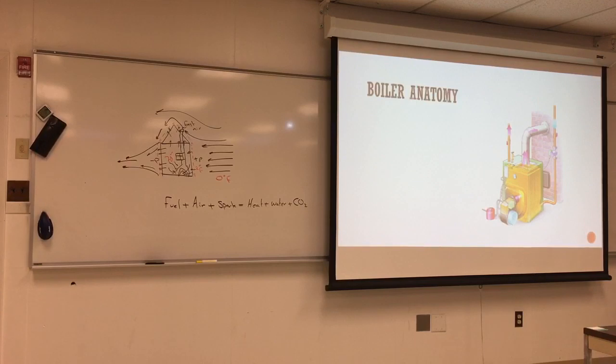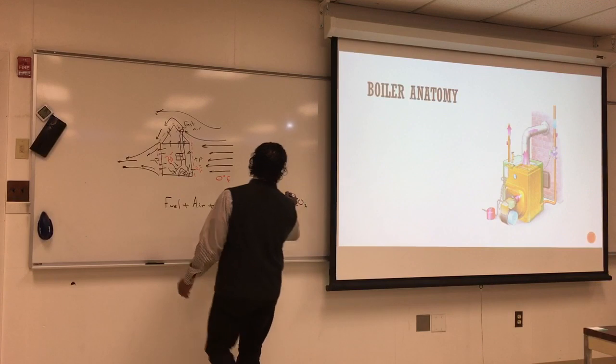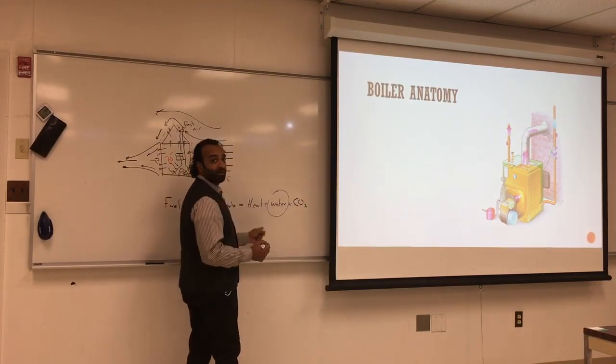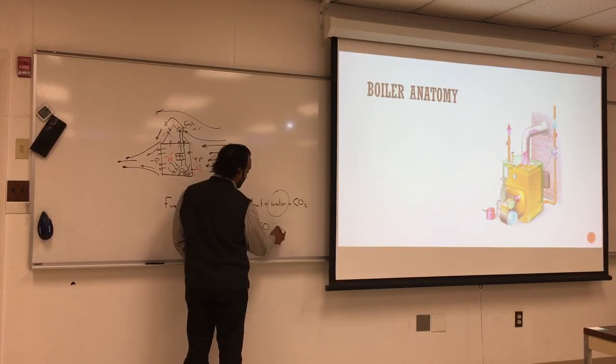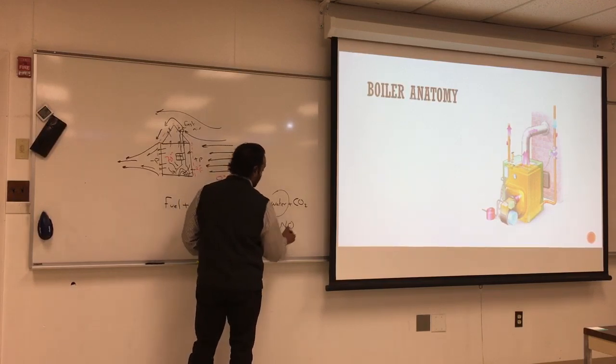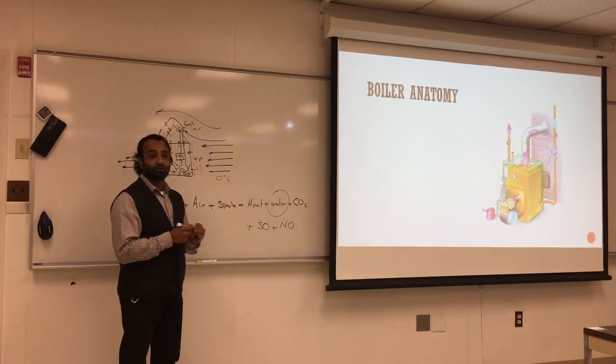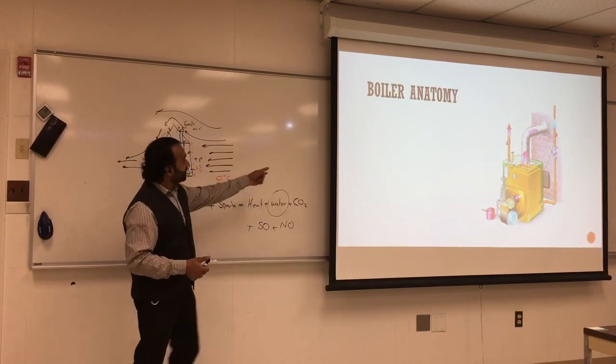What happens if your temperature at the flue pipe is 350? You'll think, hey, I'm absorbing more heat. But what does that mean? Water will condensate inside. And it's not always just water; there are some other things that we don't want, which is sulfur oxide and nitrogen oxide. They're going to dissolve in the water and eventually in the pipe.